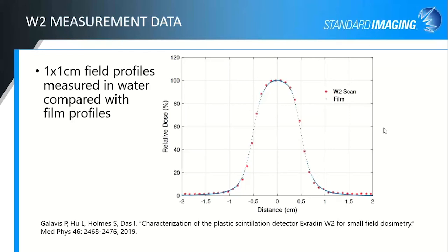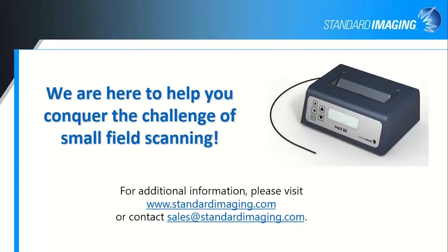This is a plot from a publication from Paulina Galavis showing the comparison of the W2 measurements in the red dots with a radiochromic film scan for a 1 centimeter field. Excellent agreement there, even out here with these low signal tails. And we've had a lot of people very happy with it for their scanning since that publication a couple of years ago too. So with that, we're here to help you. We can conquer this small field scanning challenge.